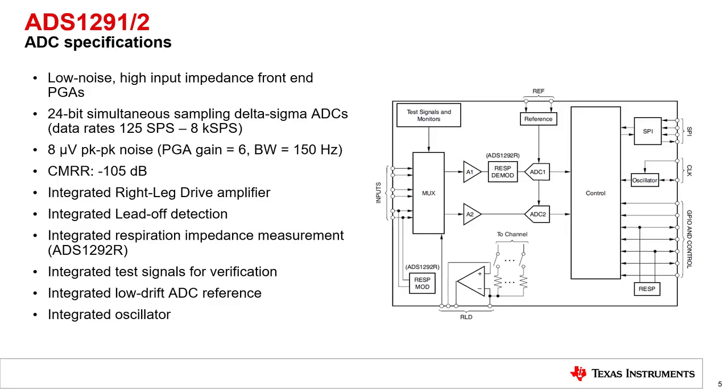The ADS1291 and ADS1292, which are the 1- and 2-channel AFEs, have similar performance specs. These devices have very low noise, high-input impedance front-end PGAs, and 24-bit simultaneous sampling delta-sigma ADCs, which can support data rates from 125 SPS up to 8K SPS.